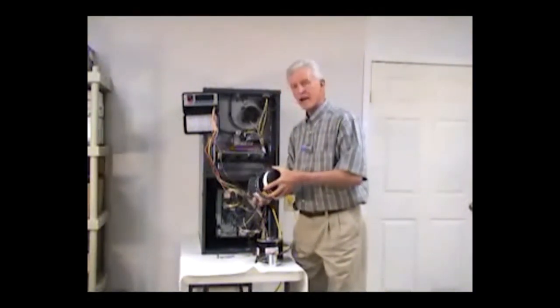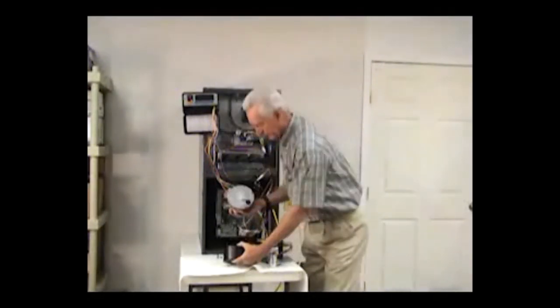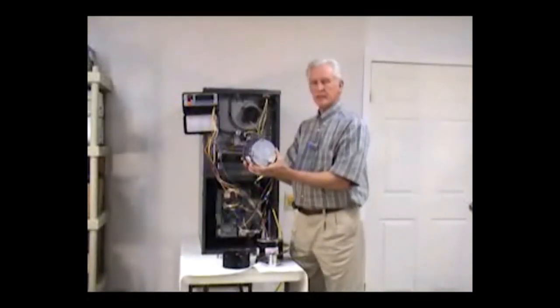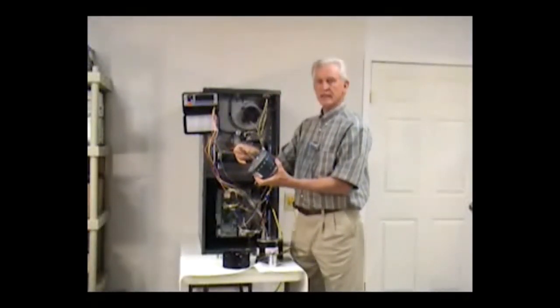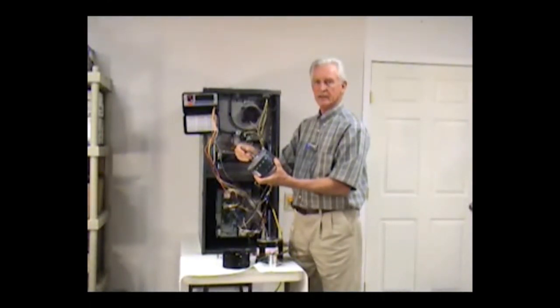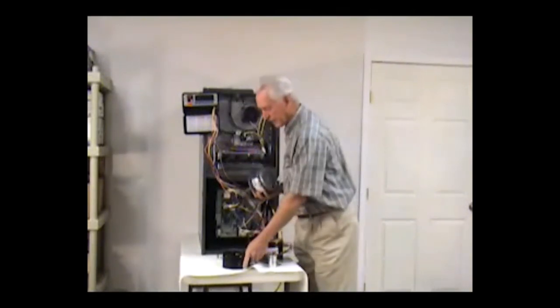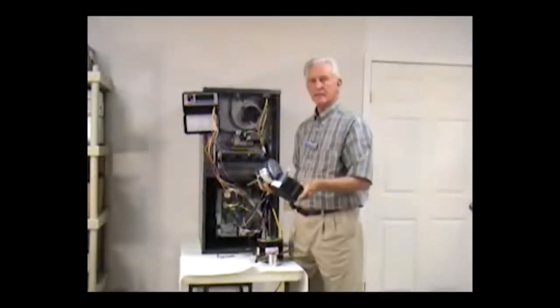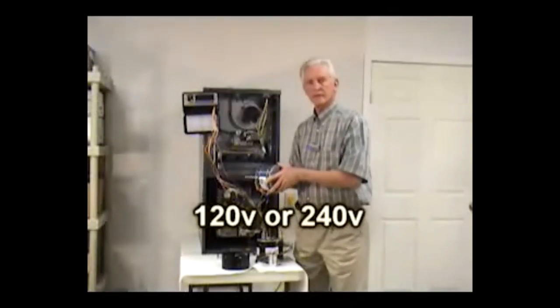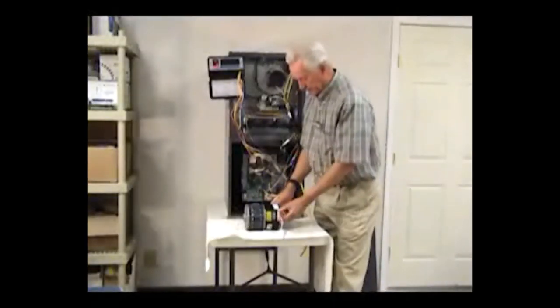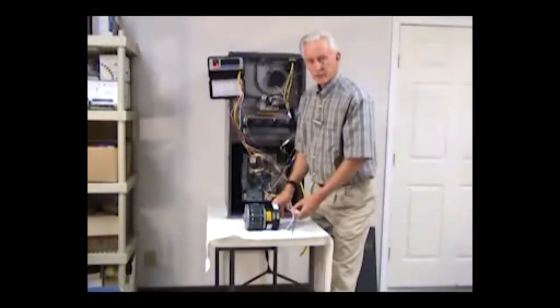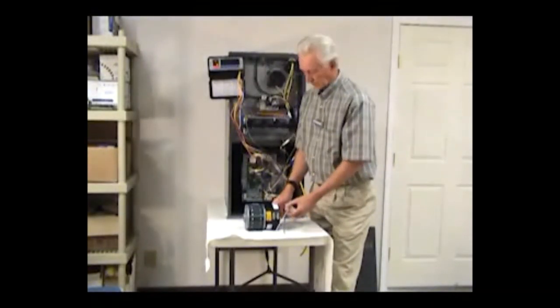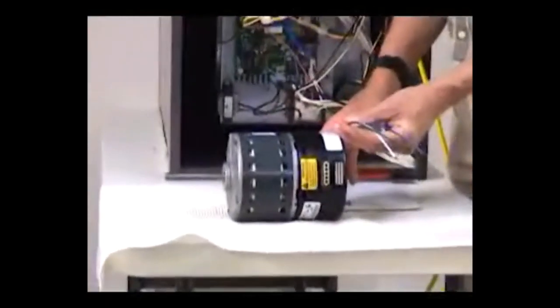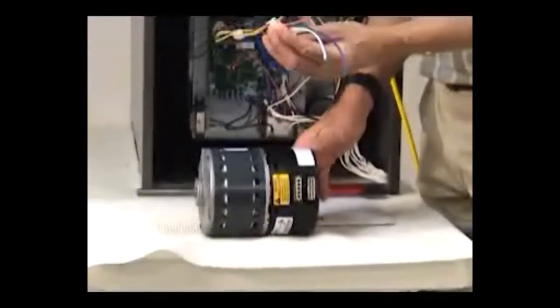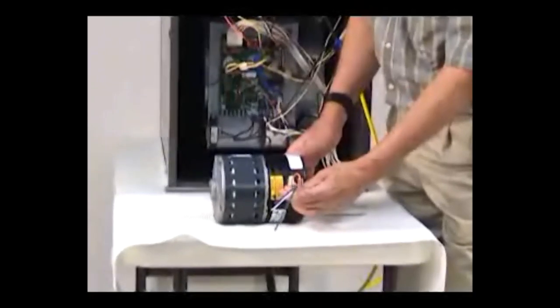The quick find out for that is to remove the module, unplug the module to where you have nothing but this in hand, and then see if you have release of the shaft itself as far as the tightness of the shaft turning. When you have done that, you have probably just found out that you have a problem really in the module and not within the motor itself. Every ECM motor can be used either on 120 or 240 volts. The arrangement for accepting that voltage will be done through the clip that you have that fastens onto the line voltage side of the motor.